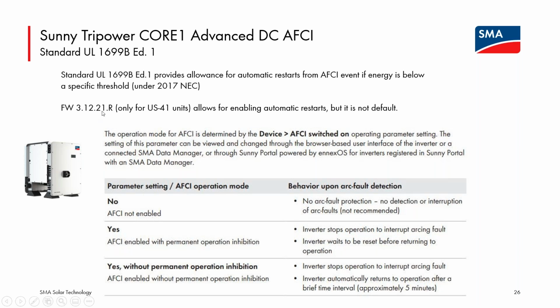But now with this firmware or higher, you have an additional choice for this parameter value: yes, without permanent operation inhibition. That means allowing for automatic restarts if the incident energy is low enough and the extinguishing time is fast enough. There will still be a disruption in the inverter production, but if you have chosen this without permanent operation inhibition and the arc was again low enough energy, extinguished fast enough, you can have the inverter go back into production.